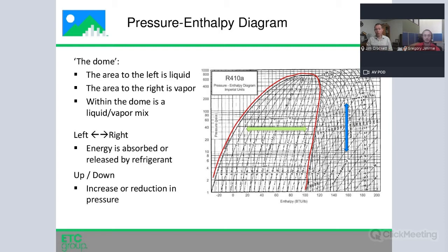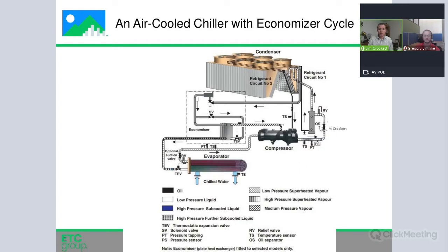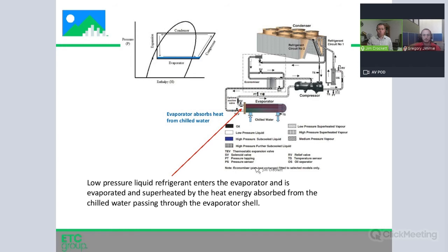Now I'll very briefly walk through one iteration of the refrigeration cycle with an air-cooled chiller. This particular air-cooled chiller has an economizer cycle on it. With the cycle, you can really begin it anywhere you want. I'm going to begin at the evaporator. If we look at our P-h diagram, as we move from left in the evaporator, warm liquid from the building delivers heat to the refrigerant, and it absorbs heat from that. The pressure in the evaporator stays constant, and so it moves from left to right on the P-h diagram.